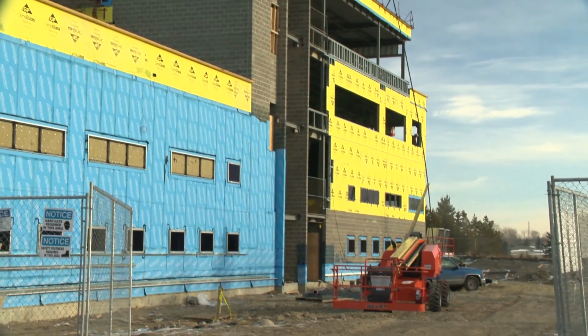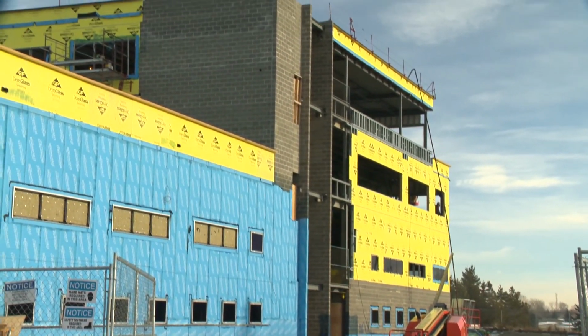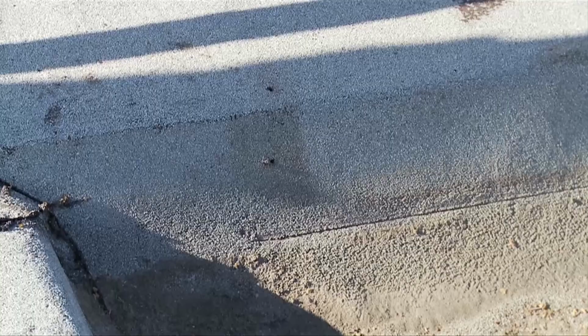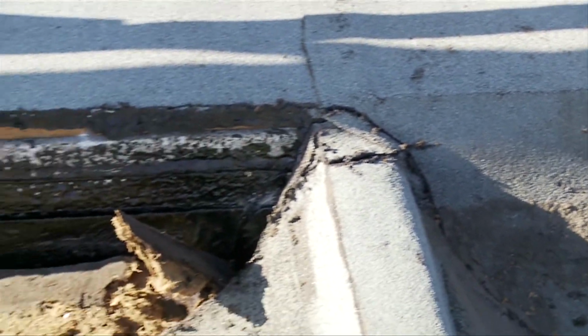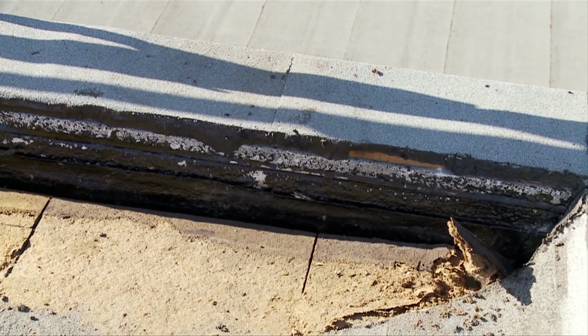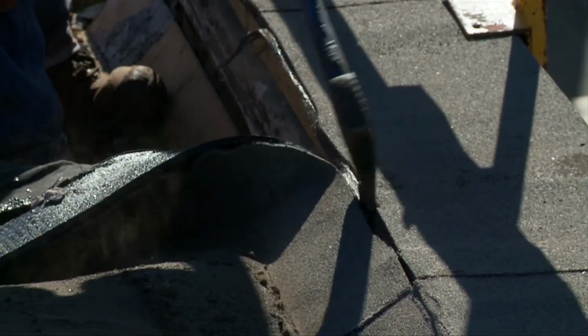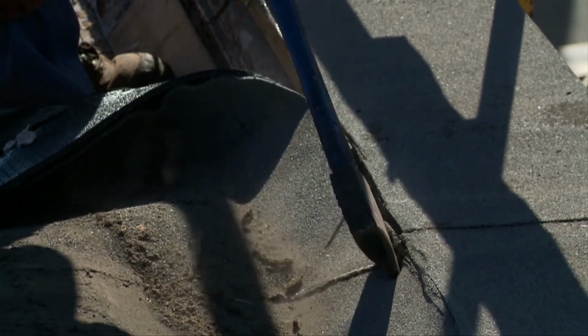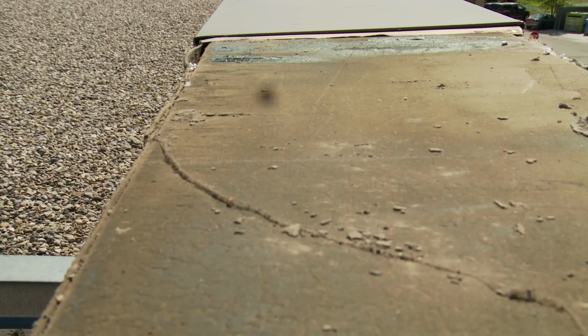We will briefly discuss the factors and the types of construction that have unique fire hazards associated with them. Re-roofing or modernization. During re-roofing, unknown construction usually is encountered with incomplete and omitted air barriers, building envelope seals, and details. During re-roofing, old wooden components exist at the curbs, parapets, and roof and wall junctions, which can be a fire hazard if not removed or replaced.